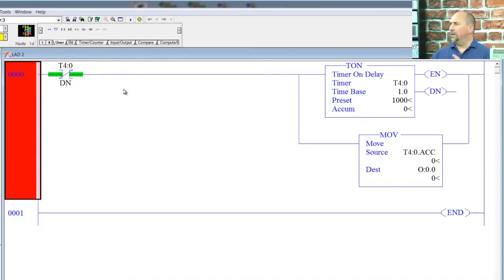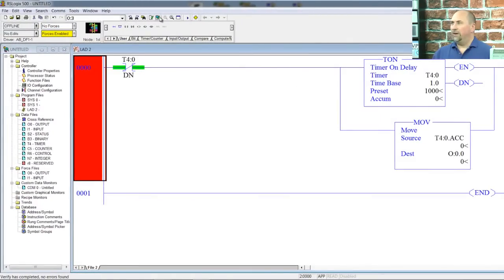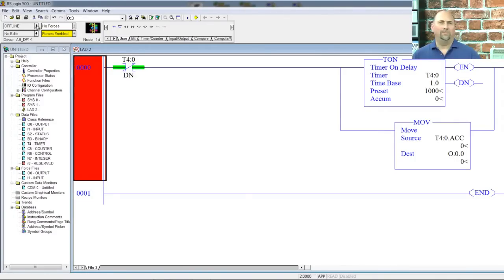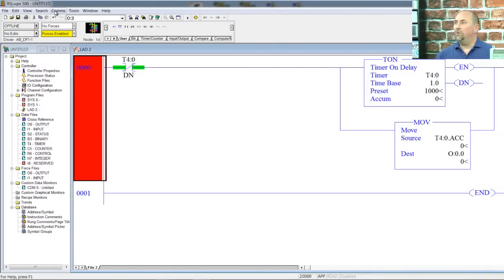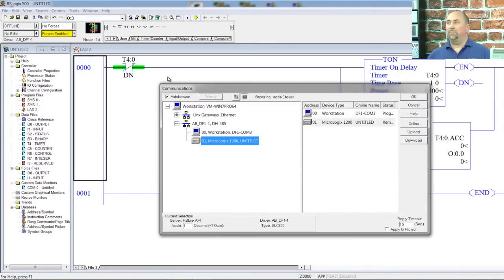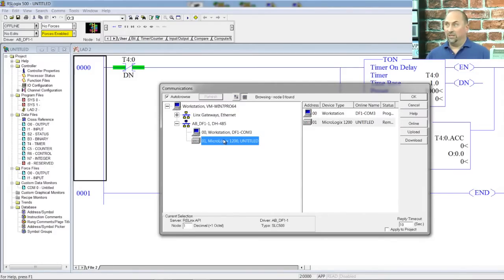Let's verify the code. If none of what I'm doing is making sense, check out one of my courses — they cover all of this in great detail. I verified the program and we had no errors, so now we have to download it. A lot of people gravitate to the drop-down here — don't, unless you've already set up the communication driver, it's not going to work. Instead, go to Comms, System Comms. That brings up RSLinx showing us the actual networks we have available and the actual MicroLogix 1200 we can select.